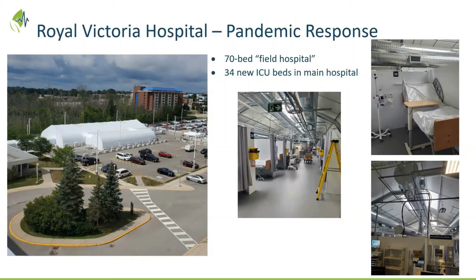It was funded primarily through Infrastructure Ontario, I believe. This isn't just for us here at RVH as the local site - it's for the whole Simcoe Muskoka region, a regional catch-all. It's not primarily for COVID patients, but for hospital surging - they're still working out how they'll implement it, but it's there should we need it for a second wave. In the middle picture, you can see how it was constructed: the central ductwork carries the negative pressure, with branches going down above each bed where you'd see a return air duct. So it takes negative pressure out of each bed space, while positive pressure is sent down the corridors on either side. It's quite an ingenious design, with its own heating, cooling, and emergency generators, though it's currently fed by power from the main building.